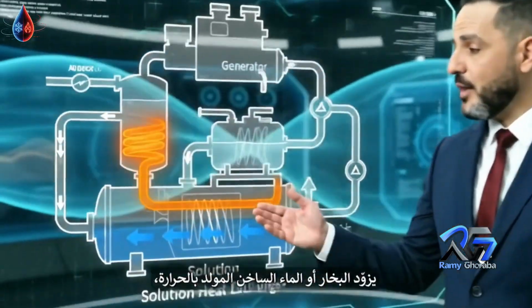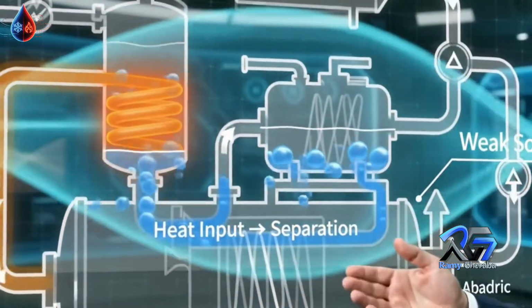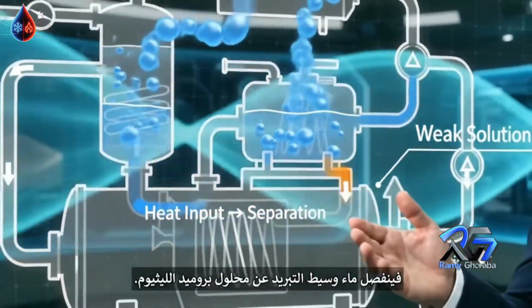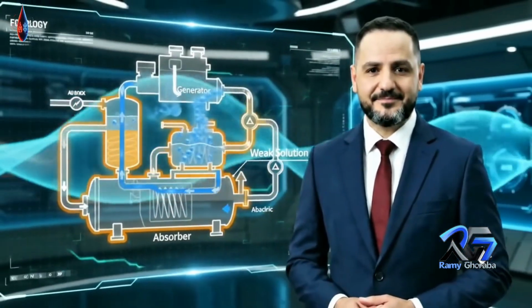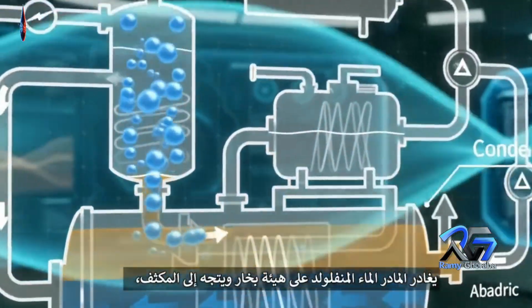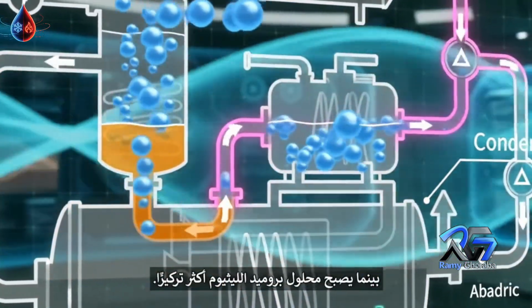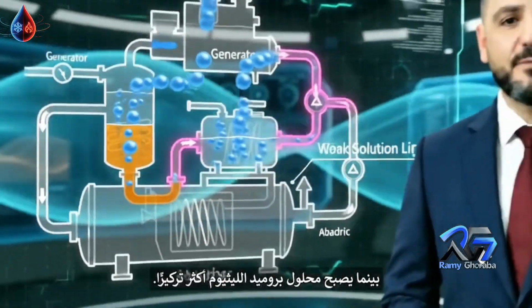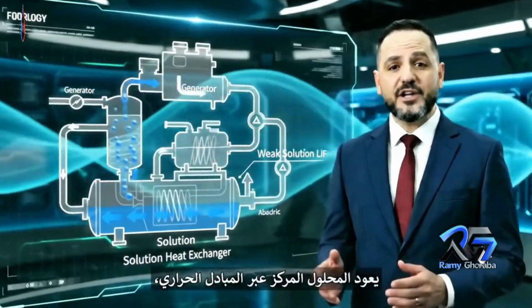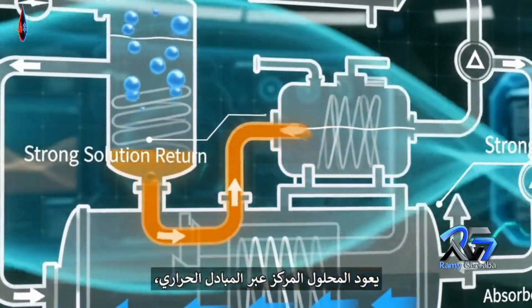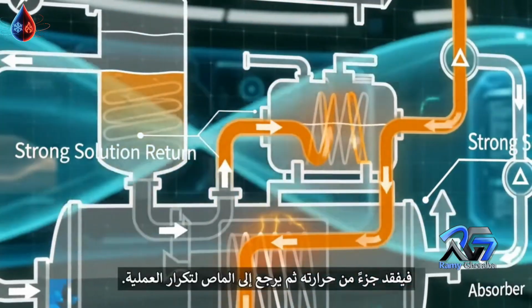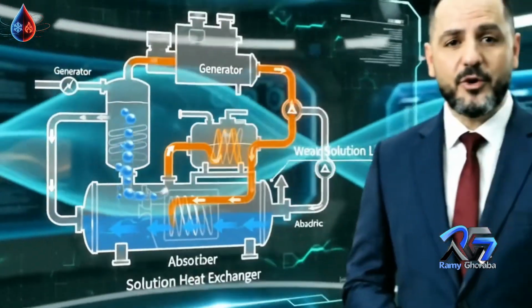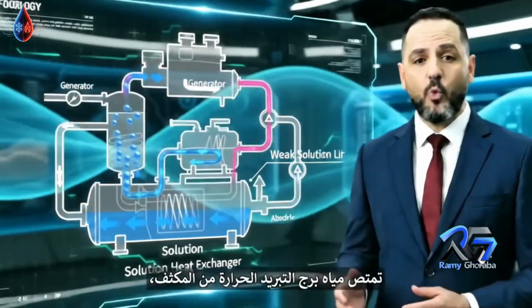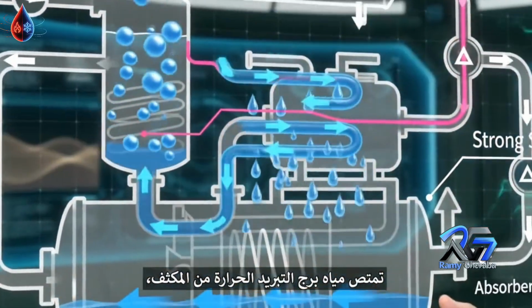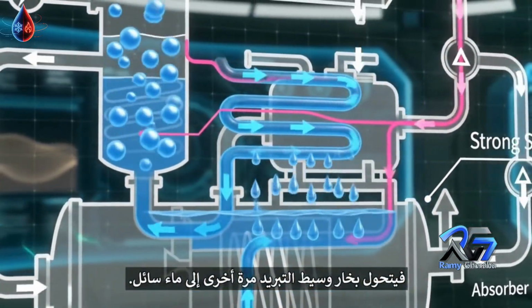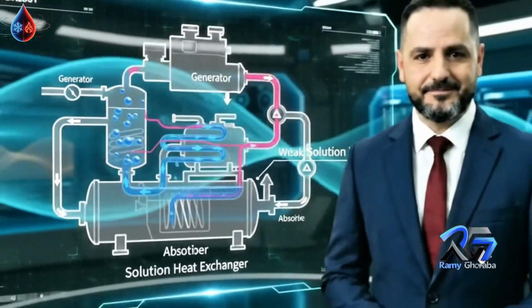Steam or hot water supplies heat to the generator, causing the refrigerant water to separate from the lithium bromide solution. Separated water leaves the generator as vapor and flows toward the condenser, while the lithium bromide solution becomes more concentrated. The concentrated solution flows back through the heat exchanger, releases part of its heat, and returns to the absorber to repeat the process. Tower water removes heat from the condenser, changing the refrigerant vapor back into liquid water.